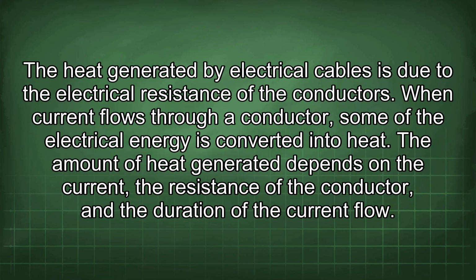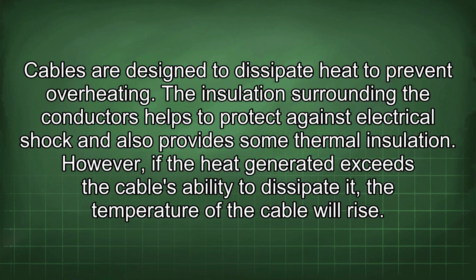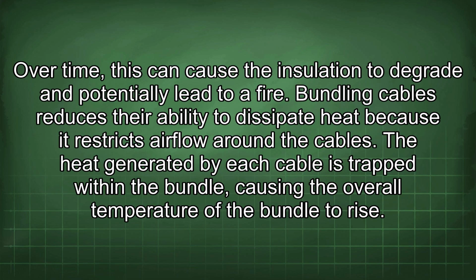The heat generated by electrical cables is due to the electrical resistance of the conductors. When current flows through a conductor, some of the electrical energy is converted into heat. The amount of heat generated depends on the current, the resistance of the conductor, and the duration of the current flow. Cables are designed to dissipate heat to prevent overheating. The insulation surrounding the conductors helps to protect against electrical shock and also provides some thermal insulation. However, if the heat generated exceeds the cable's ability to dissipate it, the temperature of the cable will rise. Over time, this can cause the insulation to degrade and potentially lead to a fire.